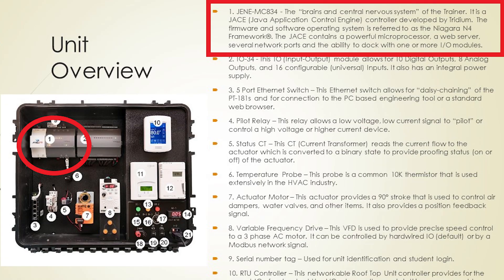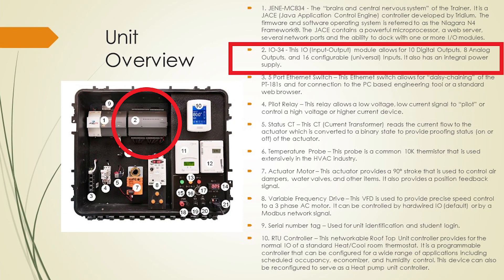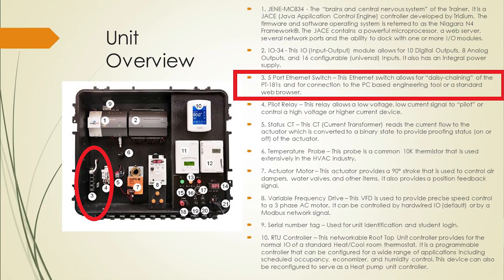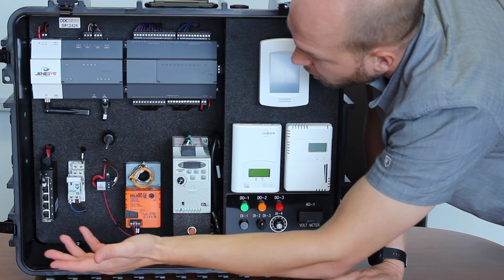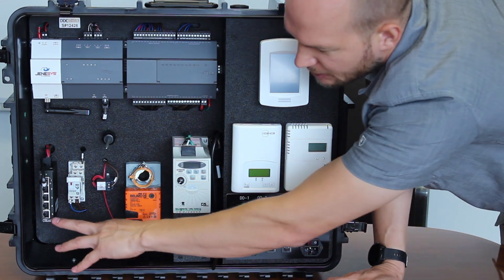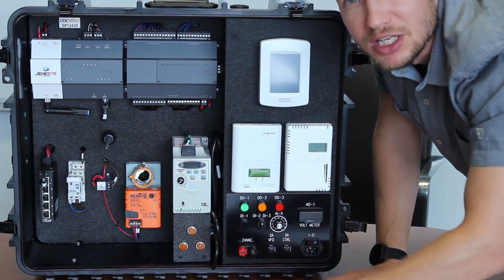You have your controller — this is a JACE, the JACE 8000 we talked about in previous videos, it's the microprocessor. Then you have the IO input/output module, which allows 10 digital outputs, 8 analog outputs, and 16 configurable inputs. You also have an Ethernet port switch — this is where you plug in the computer to access the system, or you could plug directly into the JACE.